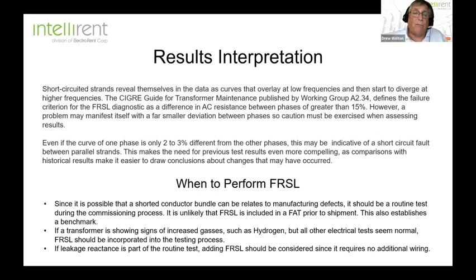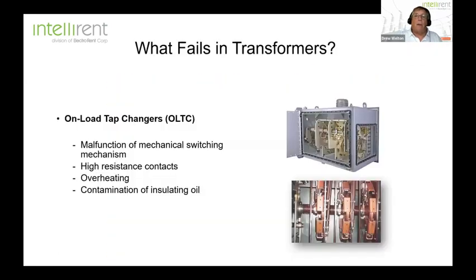So when should I do frequency response of stray losses? Well, since it's possible that the bundle can be related to manufacturing defects, it should most definitely be a part of your commissioning process. Many of these are just a little tiny checkbox in your test equipment that says perform FRSL. You might have seen that before and not known what it is, but that's what this is. If your transformer is showing any kind of gassing, such as hydrogen or others, and all your tests seem normal, this might be a good idea to run. If leakage reactance is part of the routine test, just check that box. It takes but another minute to perform and can certainly provide more information.